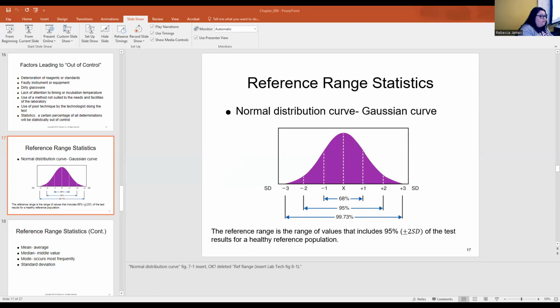And right here, the first time you ran it, you got 37, which is only 2 over your 2 SD, right? So it's pretty close. That's why you got this 1 over here, and then if you go down, it says your 1, that means it's greater than 2 SD. And that's what it was, right?